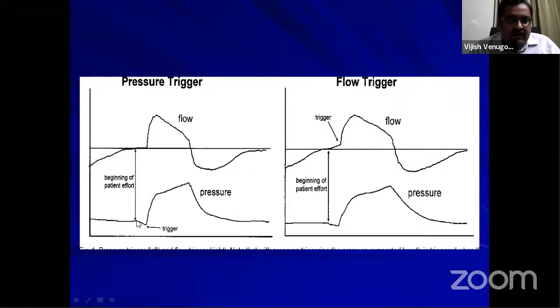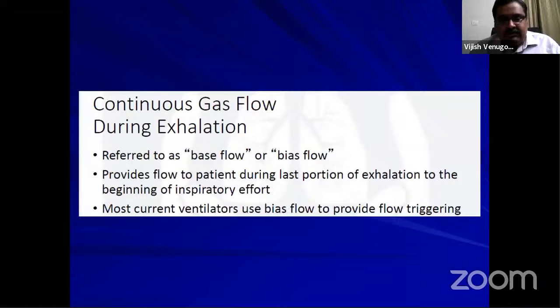In a pressure trigger, there will be a drop in the pressures from the baseline. Whereas in flow trigger, there is actually an increase from the baseline; the flow scalar just moves a little up. So that is the flow trigger. The advantage of flow triggering is that it is more comfortable for the patient, and you don't have to cause a big drop in pressure to get the breath. So flow trigger would be more comfortable for your patient.